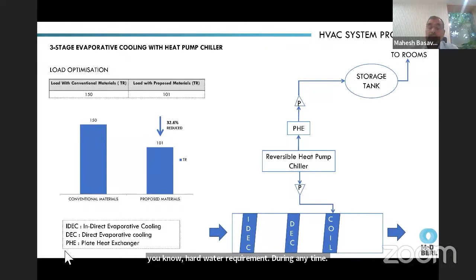In summer, the indirect evaporative cooling is on, the direct evaporative cooling is on, and the chiller is off. So you are able to get comfort with the indirect and direct. In the monsoon season, where the humidity is higher, the indirect evaporative cooling is on and the direct evaporative cooling is off, because in direct evaporative cooling you are adding moisture directly into the air. So that is off, and the chilled water is on. That's when the chiller comes on. So this is the system that we have designed.